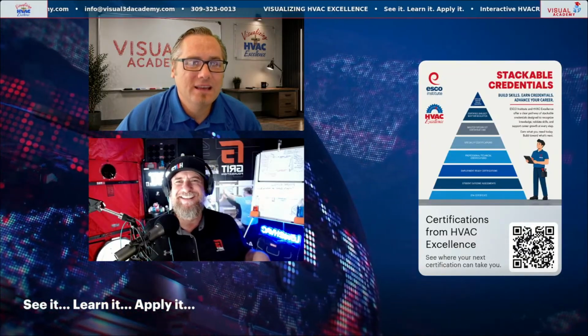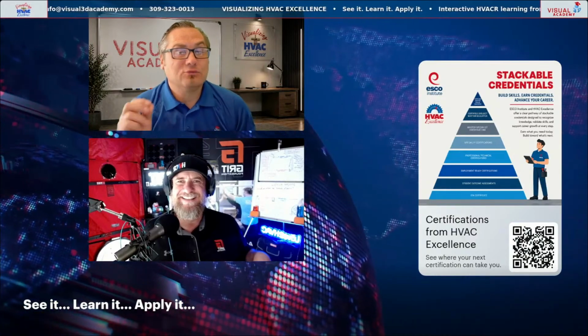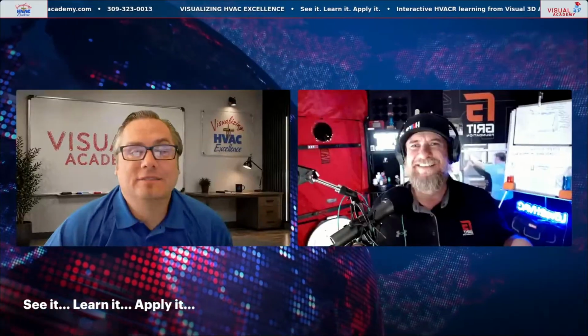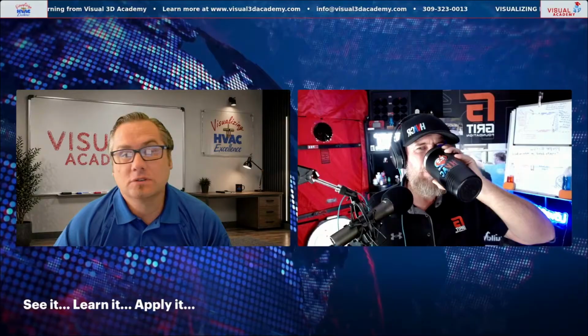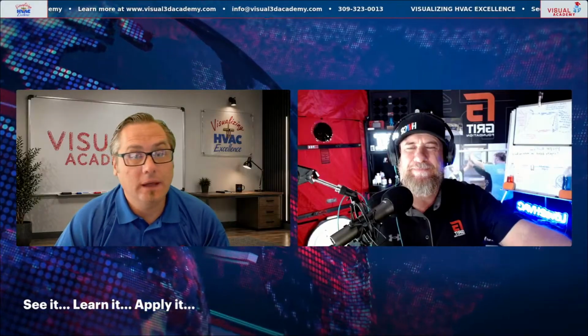So, anyway, that brings us directly into today's episode. Diagnostic foundations: know normal before you diagnose abnormal. We are not starting with an undercharged or overcharged or another fault condition. We are starting with a normally operating refrigeration system and asking what the system should be doing under those conditions. The goal is to establish a baseline we carry through the rest of the guided pathway: expected versus actual pressure, temperature, superheat, subcooling, and overall system performance, from approach to DTD to CTOA, etc.